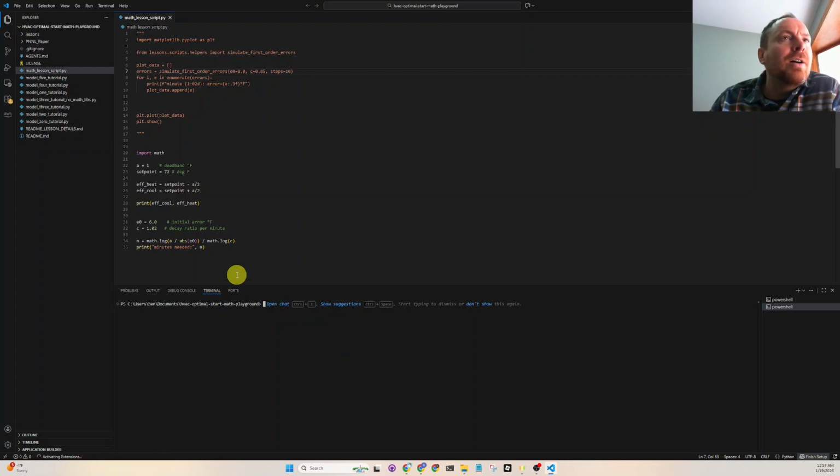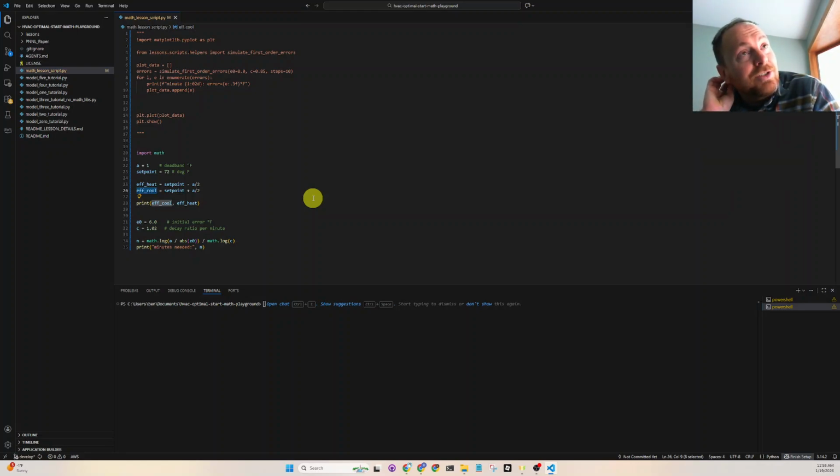So we talked about this in the last video, in degrees Fahrenheit, where I am, 72 is a typical temperature set point for a zone. And if we have a deadband of 1, that would be a half a degree up and down. So the effective heat would be 71.5 and effective cool would be 72.5, which would be an unusually short deadband. Typically what we see is a deadband of 4 degrees Fahrenheit, so like 2 degrees up and down. In the United States, there are actually energy code requirements. Code requires 5 degrees, so the engineers always design to code. And then the building automation people just kind of set up whatever they feel like.